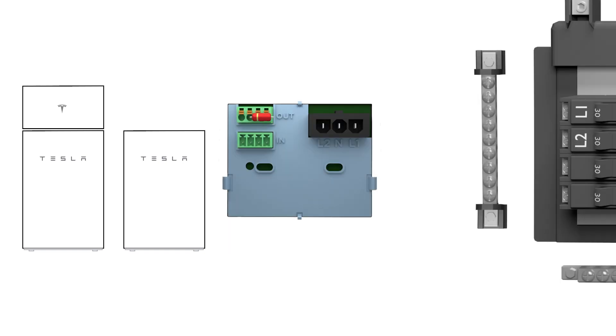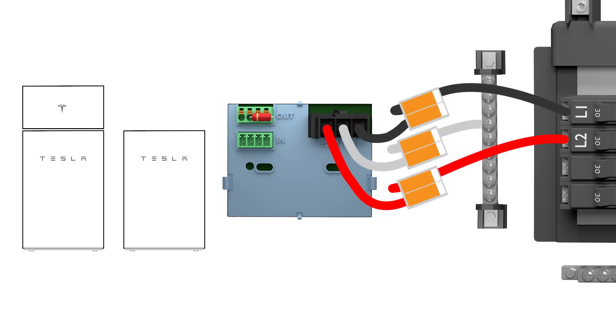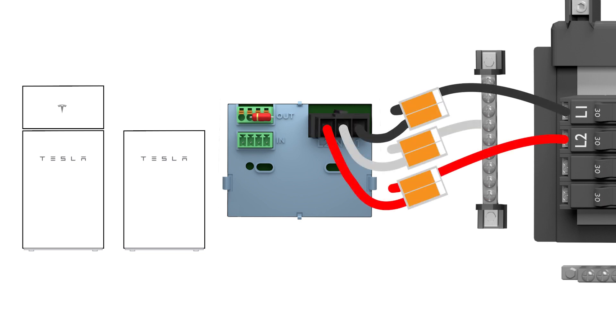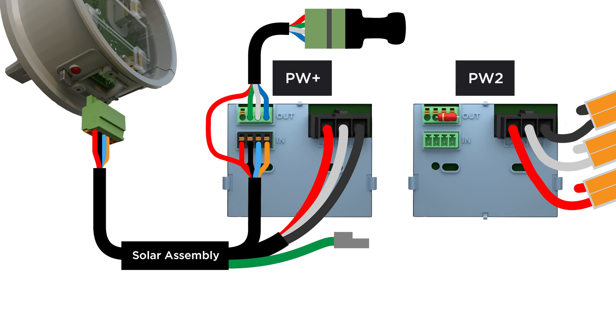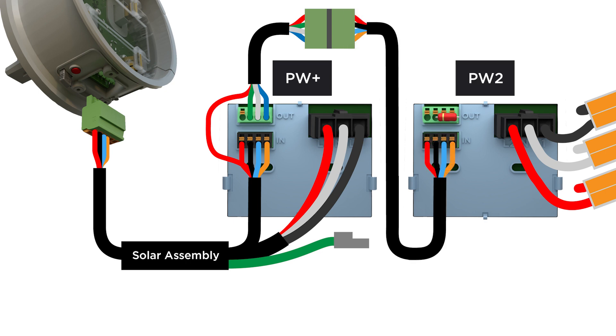Powerwall Plus can be installed with up to three additional Powerwall 2 units. Each Powerwall 2 unit will need its own AC circuit connected to a two-pole, 30-amp breaker. Communication cable must be daisy-chained from the Powerwall Plus battery assembly to each additional Powerwall.